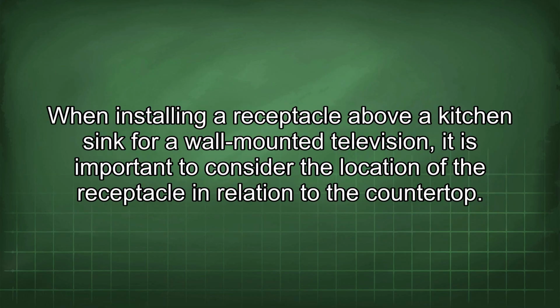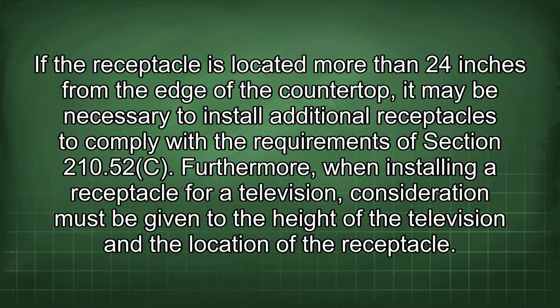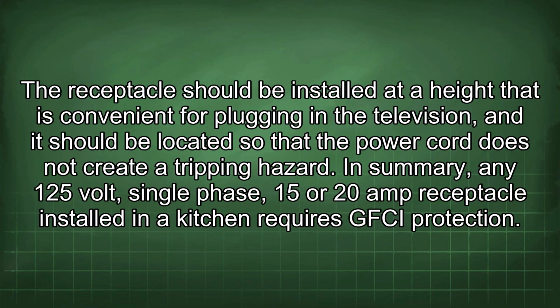When installing a receptacle above a kitchen sink for a wall-mounted television, it is important to consider the location of the receptacle in relation to the countertop. If the receptacle is located more than 24 inches from the edge of the countertop, it may be necessary to install additional receptacles to comply with the requirements of Section 210.52(C). Furthermore, when installing a receptacle for a television, consideration must be given to the height of the television and the location of the receptacle. The receptacle should be installed at a height that is convenient for plugging in the television, and it should be located so that the power cord does not create a tripping hazard.